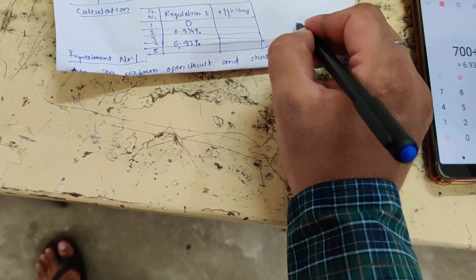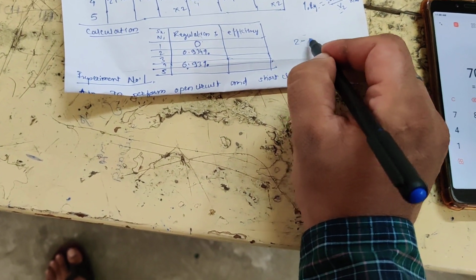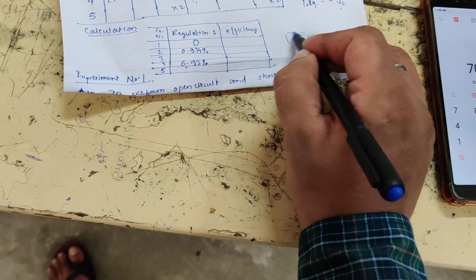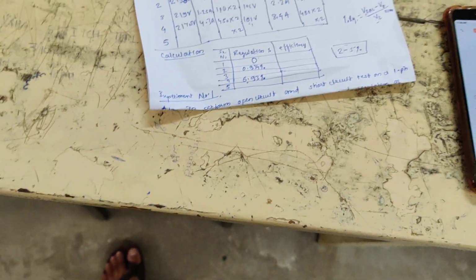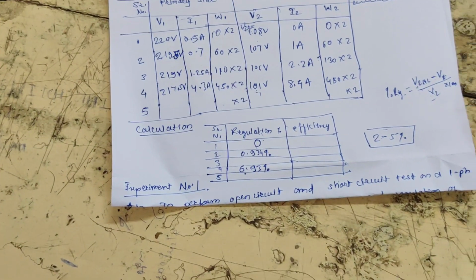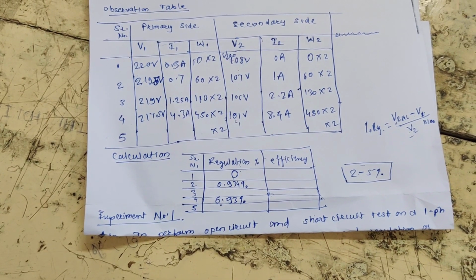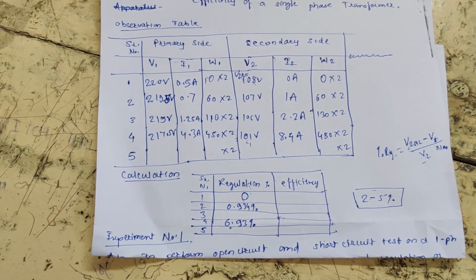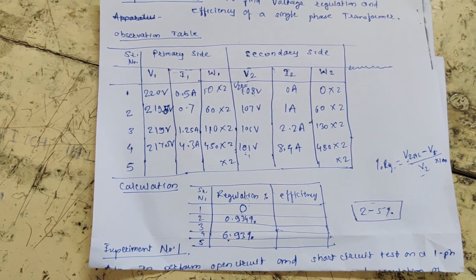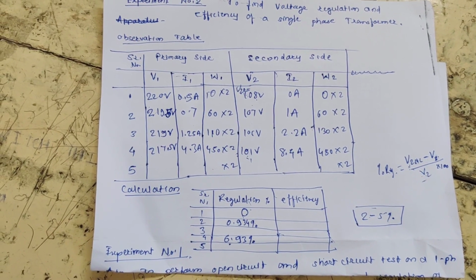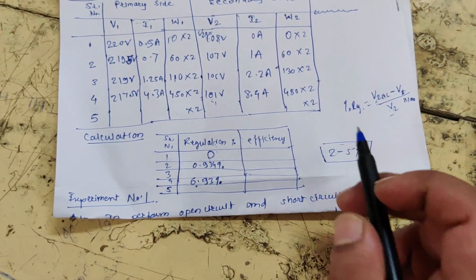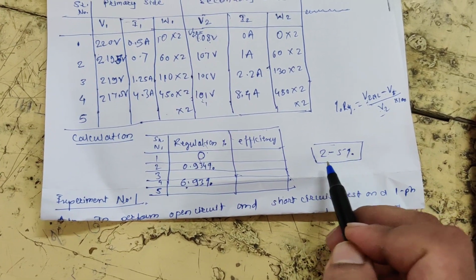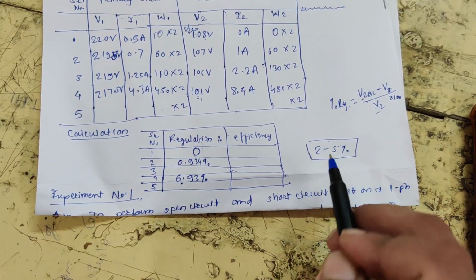Ideal regulation has to be 2 to 5%. If your voltage regulation lies in between this range, we may assume that the efficiency of this particular transformer is as high as possible. Ideal range is 3 to 3.5.